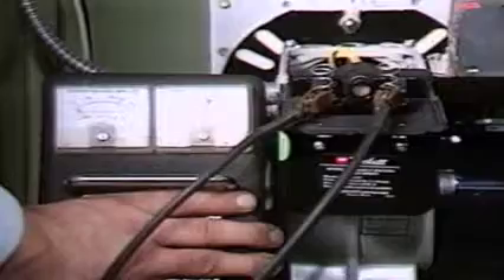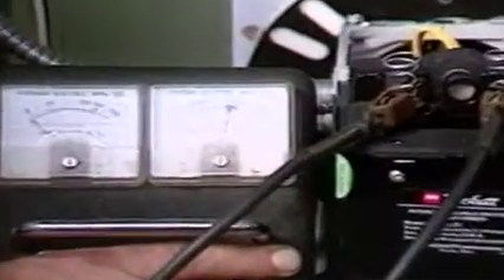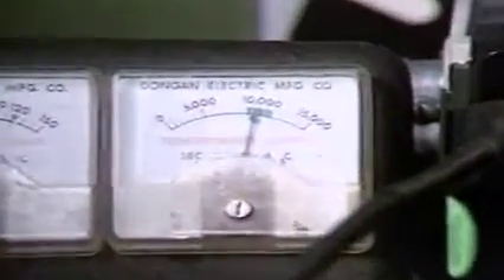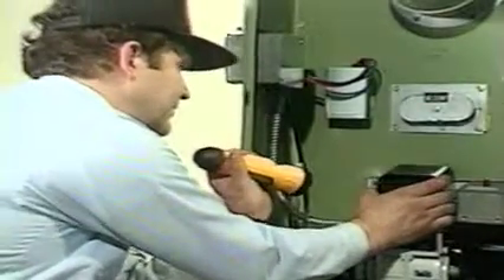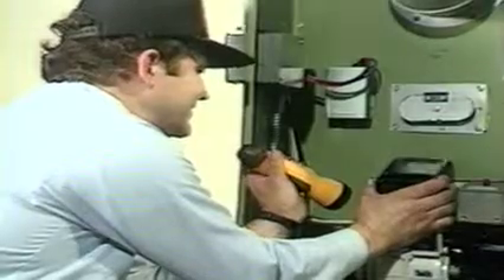In the ignition system, you have two suspects, the transformer and the electrodes. Start with the transformer, making the following electrical checks. Measure voltage between the transformer primary lead and the neutral connection. It should read 115 volts on the primary input side. Measure for a total of 9,000 minimum volts between the secondary terminals using a transformer tester. If the transformer shows no problem, look at the electrodes.